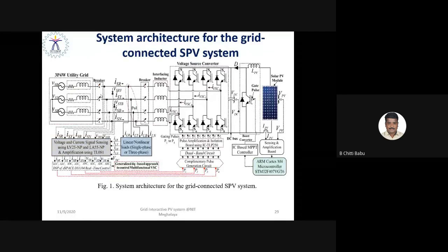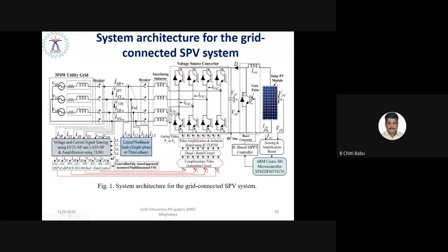And the system architecture for the grid connected solar PV system is as follows. The solar PV array generates DC power, and that will be given to the DC link via a DC to DC boost converter. That DC to DC boost converter transfers the solar PV power to the DC link, from the low voltage PV to the high voltage DC link. So it is basically boosting up the voltage, and moreover it is a candidate for maximum power extraction with the help of maximum power point tracking, right?